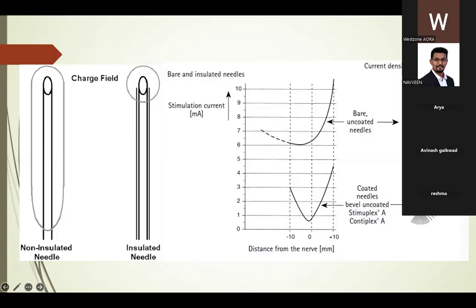As you can see here, the complete shaft and the tip of the needle are conductive, so it may require a higher current to identify or locate the nerve and cause the desired motor response. And the needles which are coated with Teflon are very precise, as only the tip is conductive, so they may require a very low stimulation current to get the desired motor response.